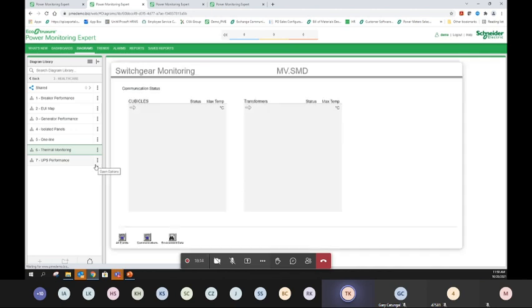Okay, this is another one of the applications. This is 24/7 real-time monitoring of the electrical joints and critical electrical assets like a generator, bus bar, and transformer. Normally you use a heat gun or optical gun to do the measurement yearly. But this real-time monitoring application uses a very small, wireless, batteryless sensor, simply put on top of the bus bar joints, the electrical connections.